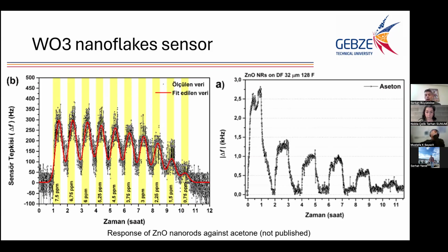The problem doesn't change, because the question can also reveal the noise problem. Here we have so many noises, and I just wonder what the sources of these noises are. Maybe it can be the chamber problem, not getting the vacuum before the measurements, or something else? It's not related to that. The main source of noise here is the precision of the vector network analyzer. Its precision is 7 ppm, which means that for the 1 megahertz frequency, it gives 7 hertz of precision.